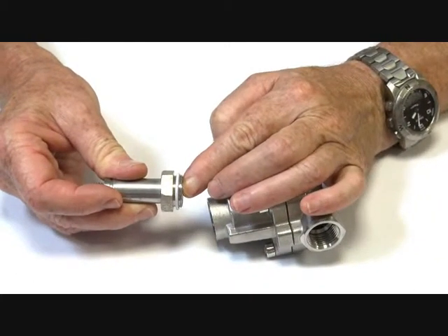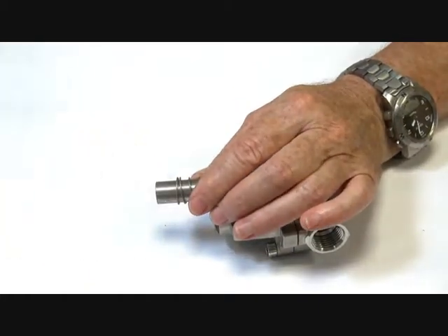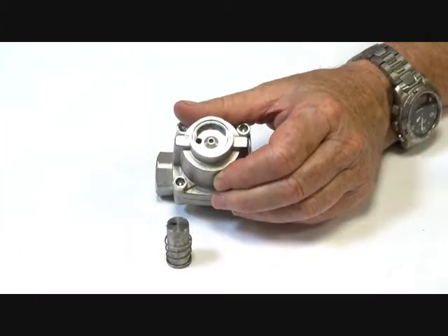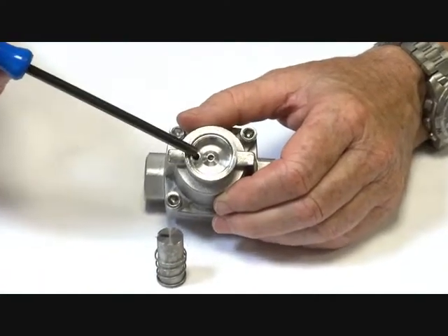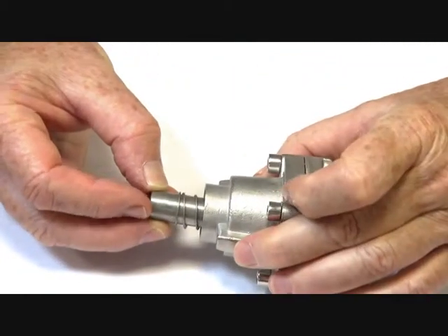When the power goes on the coil is pulled in; when the power is released, it comes back down. This armature normally sits in here on top of this jet. Inside here there is a port coming in, so the inlet port is here — media comes through this small hole in the side and sits on top of the armature.